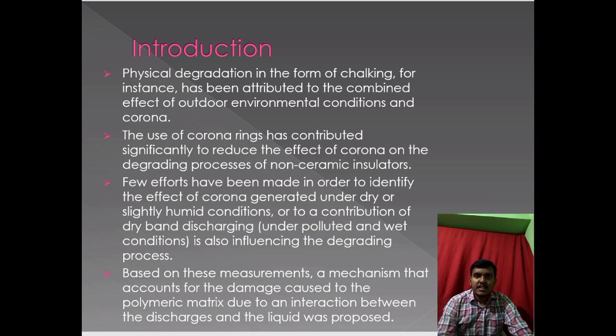So as we know, the degrading process in polymeric material is mainly due to the corona discharge. Use of corona rings significantly reduces the effect of corona, but not fully. Even if new materials with enhanced electrical properties are available, as long as the insulator is subjected to high voltage, the influence of corona on mechanisms of degradation of dielectric material cannot be completely eliminated. Until now, only few efforts have been made to identify whether degradation observed at the energized end of a polymeric insulator is due to the effect of corona influencing the degradation process.